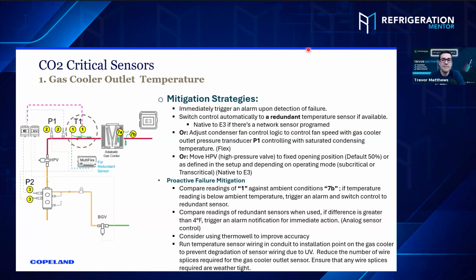Yep. And so if you do happen to have a T1 failure sensor go, ideally you can immediately trigger an alarm. You're going to see that everywhere. Number one, trigger an alarm, let somebody know. Number two, switch control automatically to a redundant temperature sensor if it's available. And we're starting to hear a lot more chatter amongst the end users that we talk to, who are specifying dual sensors on the critical sections of the system. Now in the E3, it's native if the network sensor is programmed. So as soon as you get an open sensor on one, it'll default, and you wire your redundant sensor to a MultiFlex board. The alarm's gone out, and your system's not going to crash because it's being controlled by the redundant sensor.